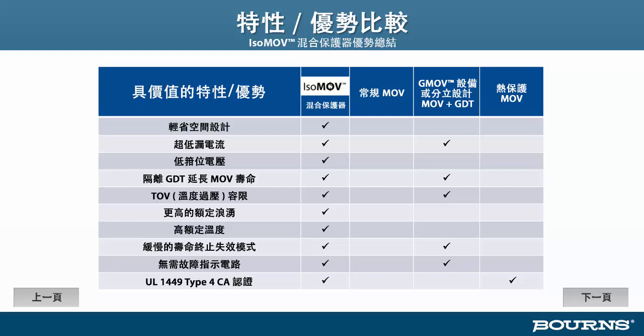You can see, just going down the list, the IsoMOV protector has a space-saving form factor. We talked about how you can achieve the same surge capability on a smaller part. You achieve the ultra-small leakage current, which can help you with Energy Star ratings, and can certainly help with any other leakage current test requirements you might have. The IsoMOV protector has a lower clamping voltage for particular surges because it does a better job of distributing that current across the MOV. It has the isolation built in. It extends the MOV's life because it doesn't continuously age with constant leakage current and constant exposure to the AC line. The IsoMOV protector is more tolerant of temporary overvoltages than conventional MOVs or thermally protected MOVs.